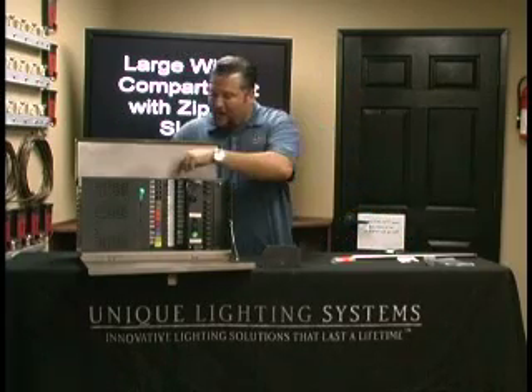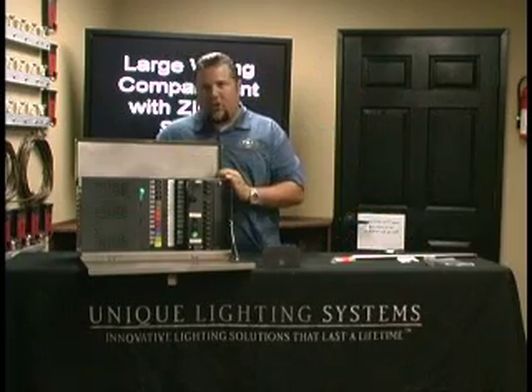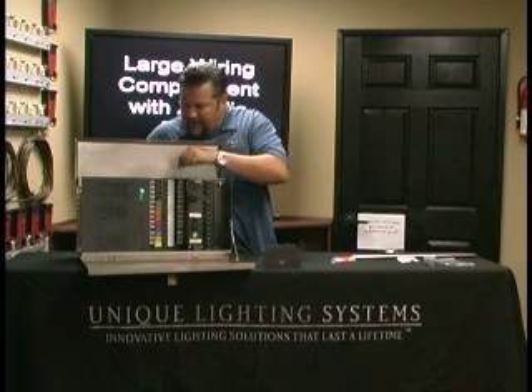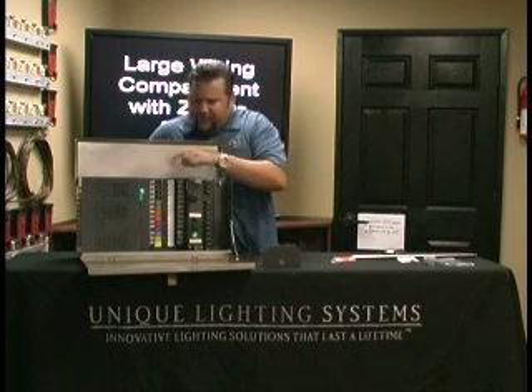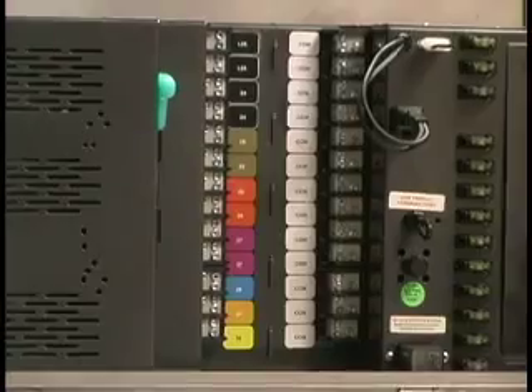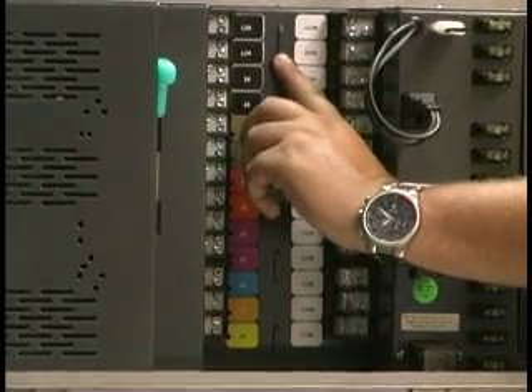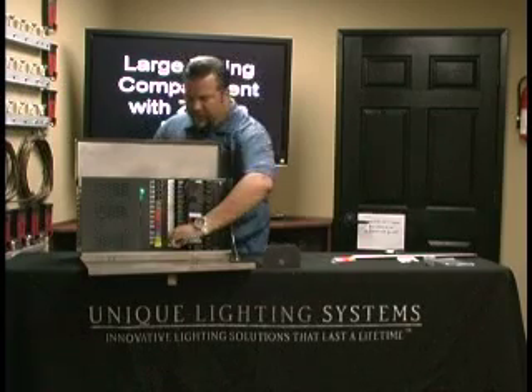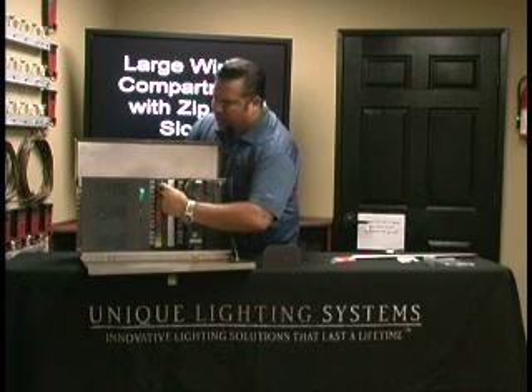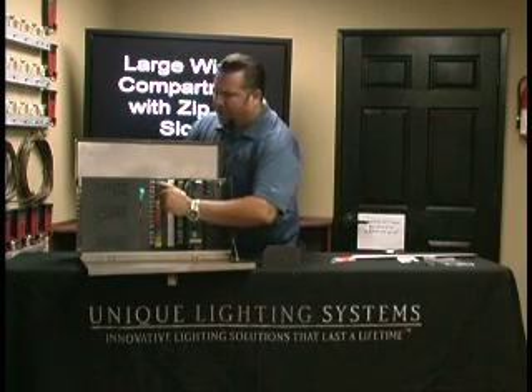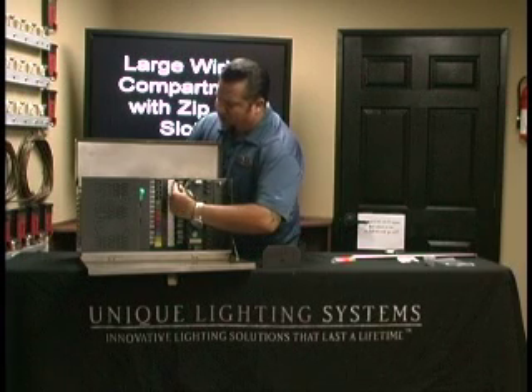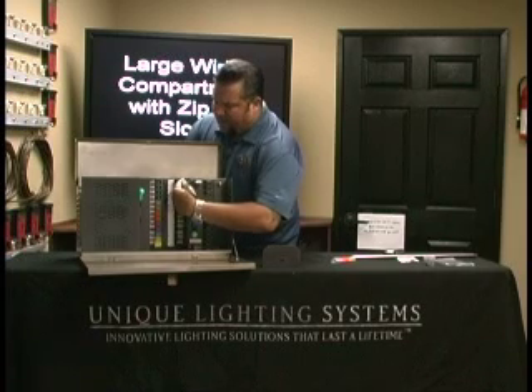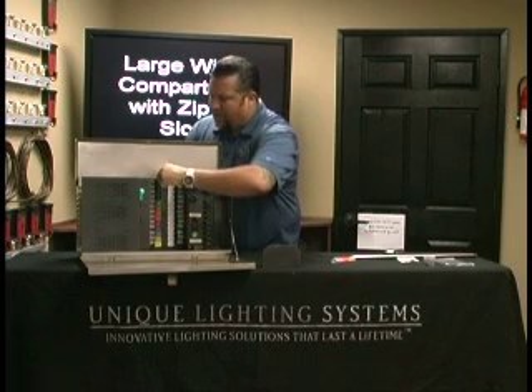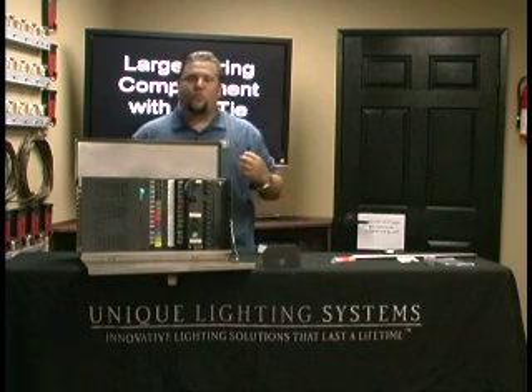The part I was getting to is the large hardwire, or wiring compartment. You can see—we'll try to zoom in—we've got these slots here for zip ties. So when you run your wires up through your conduit from the bottom, you can split it off depending on what voltage tap you'll be using. You can pull your home run common side directly to the tap or the common on this side, then run a zip tie through here to zip tie it off so it's really clean.